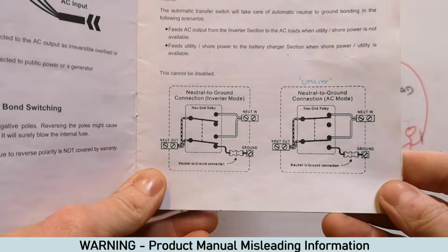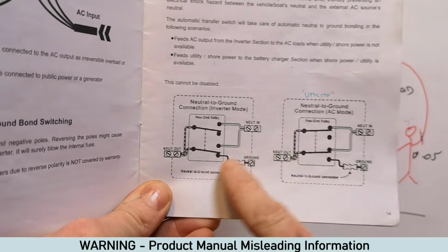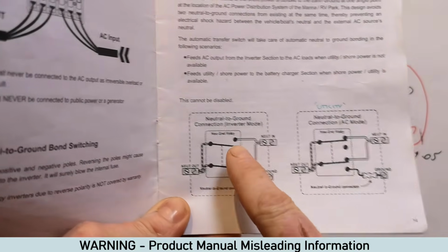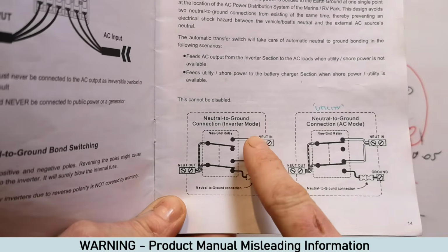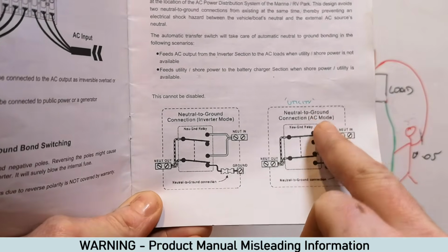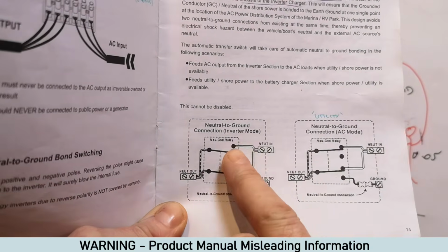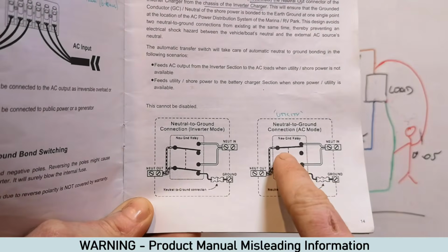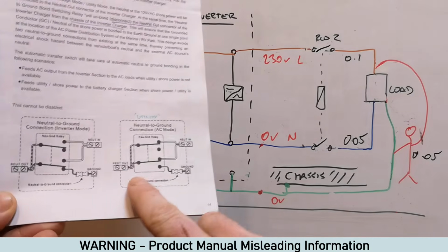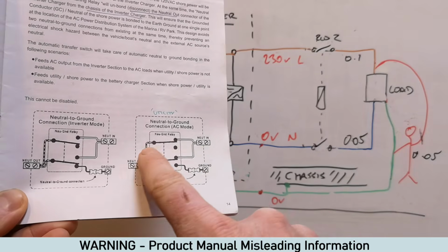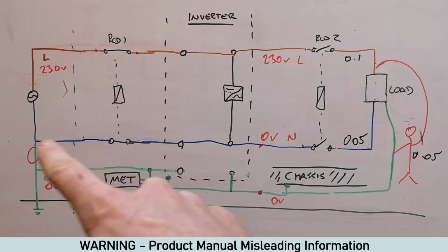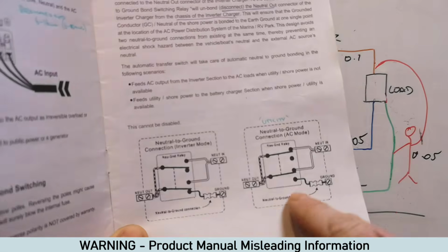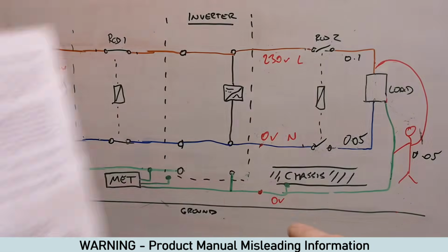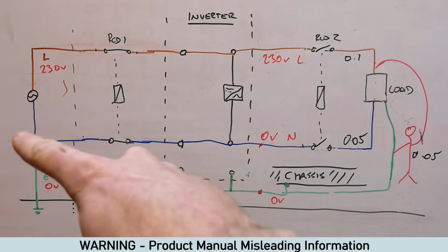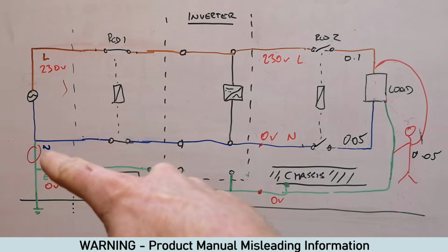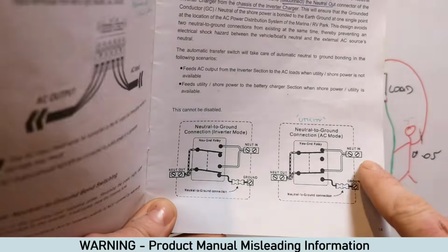This is where we were misled. Now this is what I've just explained. So neutral to ground connection in inverter mode, neutral to ground connection AC mode. AC mode's on hookup, that's obviously non-hookup. So hookup, like it is here, you can see that the neutral in is linked to the neutral out. They're not connected to ground at all, which is correct. They're not connected to ground except for this point at the source here, which is before this connection.